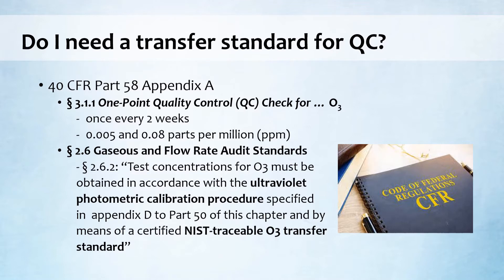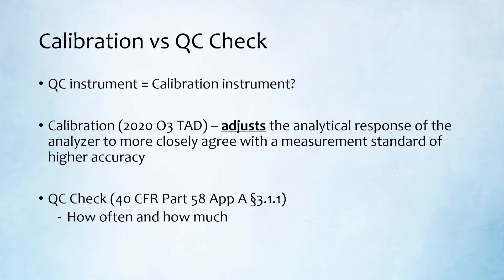In Section 2.6 of the same appendix, the CFR says pretty clearly that for both audits and calibrations, your instrument needs a photometer and needs to be a transfer standard. A lot of confusion results from the use of different terminology across the different guidance documents. The CFR details that equipment used for calibration requires a photometer, but it doesn't explicitly define calibration. And the definition for QC check is even more vague, essentially just going into how often and how much.